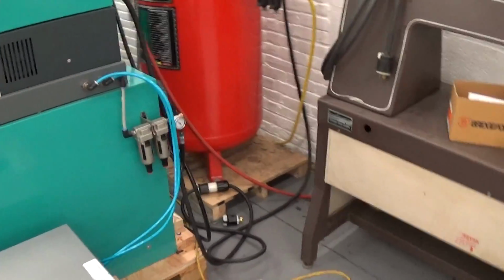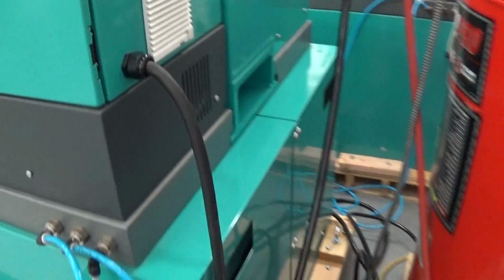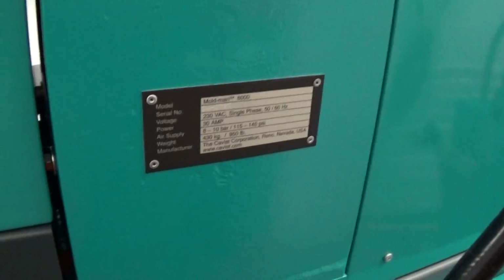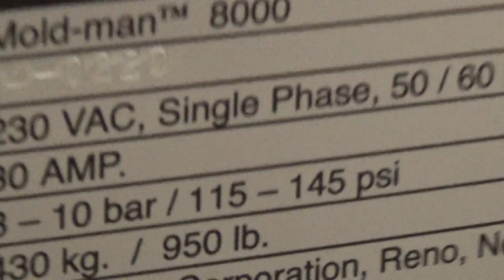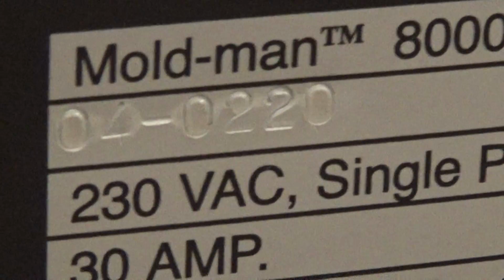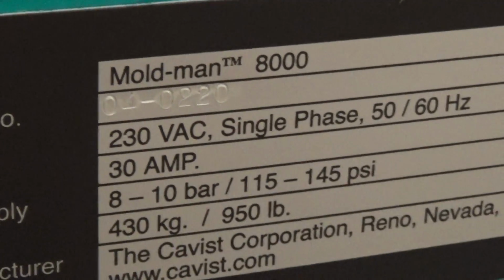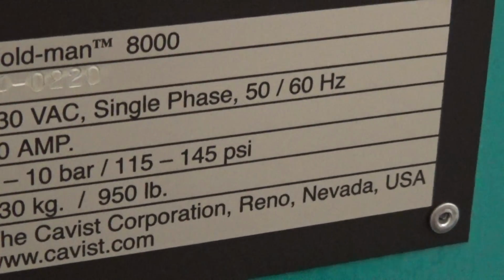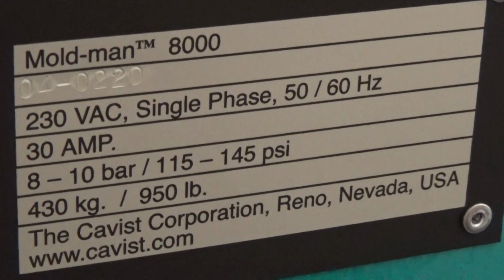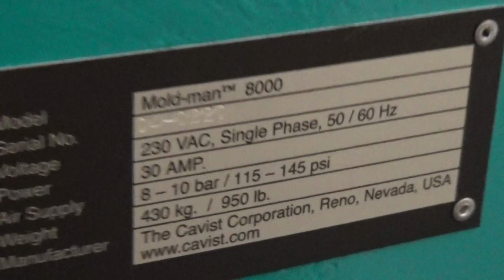This unit, I'll go to the tag. We already got it warmed up by the way. This unit, serial number 040220, is a 230 volt single phase unit, 50 or 60 hertz. It draws 30 amps. It's going to come with this Polyscience chiller.